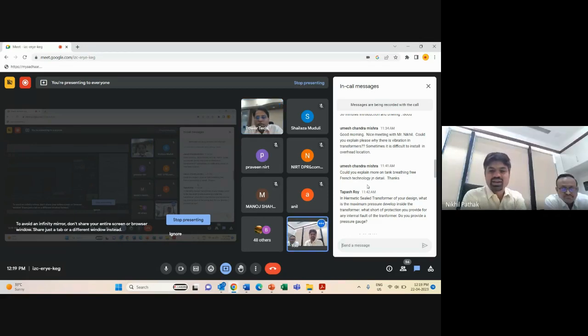Yeah, I can read that. It's a very good question. The first reaction to this question is that any and every oil-cooled transformer has to have a pressure gauge, otherwise it will become a bomb. So we do have a pressure gauge in our transformer. We are giving two options to handle abnormal pressure in the transformer. One is the manual pressure device, which has a mechanical gauge. It will have a float, as in the case of a normal transformer. So the manual pressure gauge is what we call a pressure relief valve or pressure relief device, manually operated. It will operate if the designated pressure is crossed.